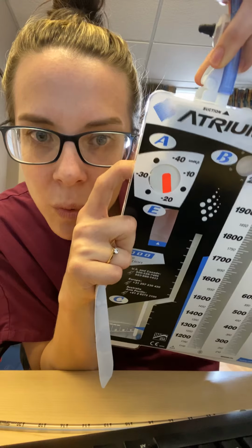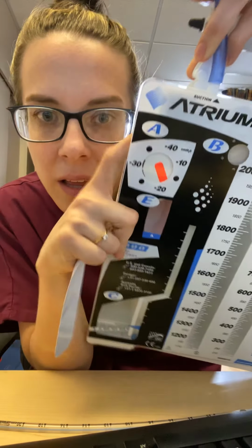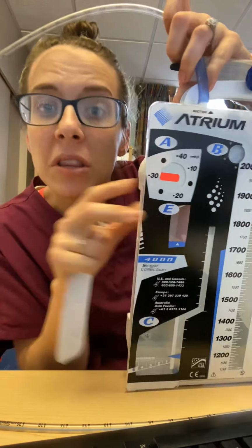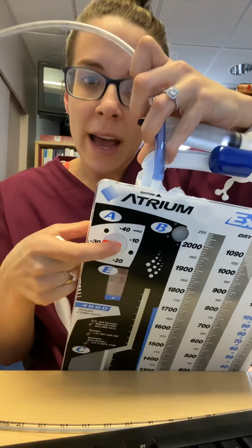Oh, by using this dial right here. See that little lever right there? So right now we're at -20, and I'm going to move it to -30. So again, I'm just moving this lever right here, which is behind the suction control chamber. Now we're at -30.